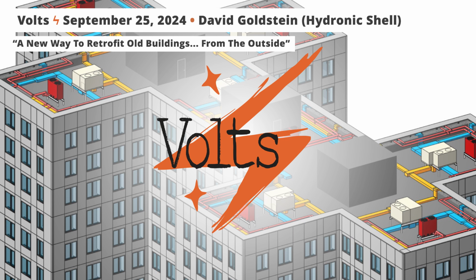That's right, 6 inches. And so fortunately, the ducting and piping is all very standard components that you can get at any HVAC shop that any contractor is familiar with. Sheet metal duct, galvanized sheet metal, we'll have it, depth of it being anywhere from 4 to 5 inches so that it can fit within that 6-inch cavity. And that's standard ductwork in the industry. And then the piping is also quite small. Again, the loads in the building are very low. So that means you don't need a lot of hot water and chilled water to the spaces.